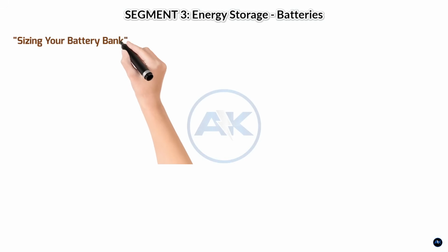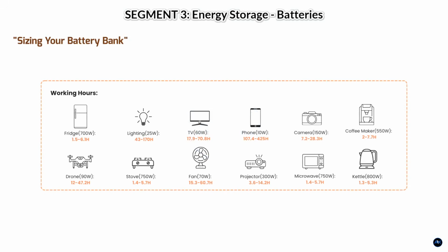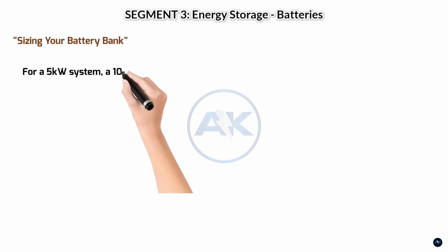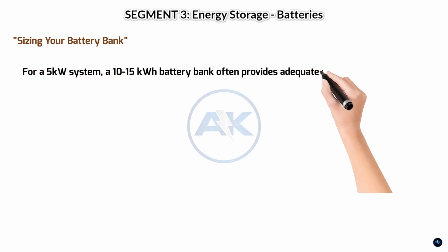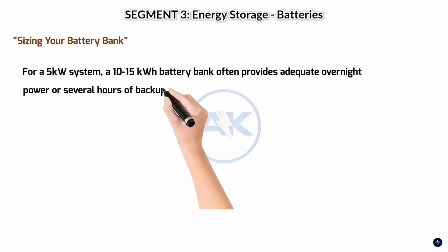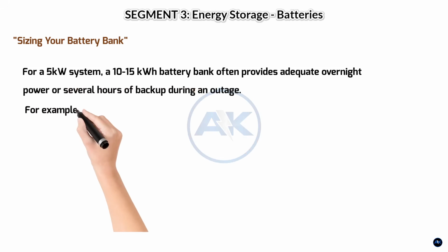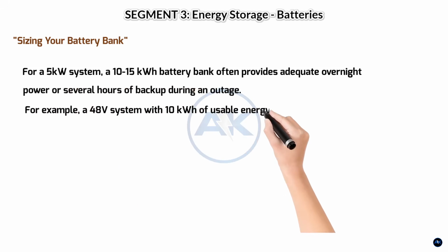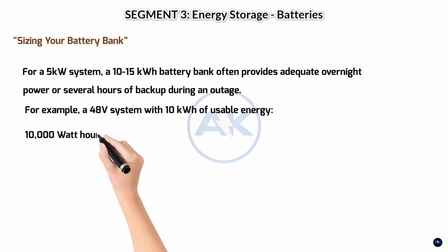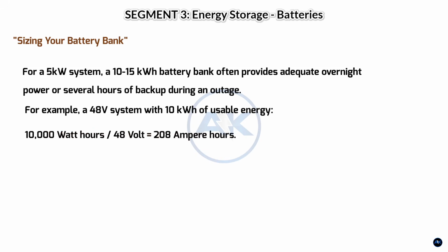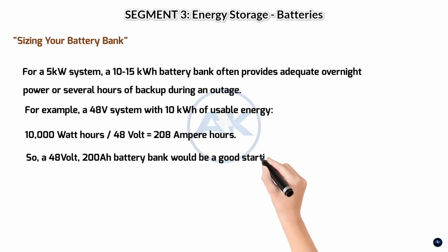Sizing your battery bank. This depends on your daily energy consumption and how much backup time you need. A typical home might use 15 to 20 kilowatt hours per day. For a 5 kilowatt system, a 10 to 15 kilowatt hour battery bank often provides adequate overnight power or several hours of backup during an outage. For example, a 48 volt system with 10 kilowatt hours of usable energy: 10,000 watt hours divided by 48 volts equals 208 ampere hours. So a 48 volt 200 amp hour battery bank would be a good starting point.